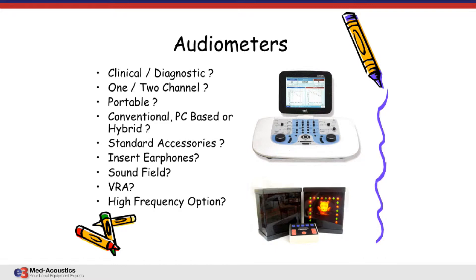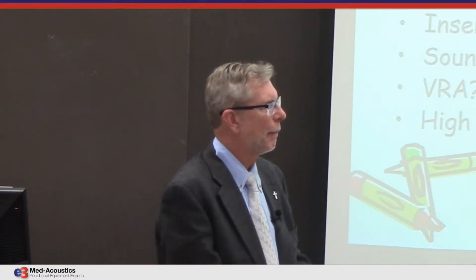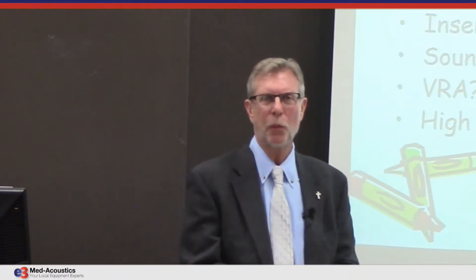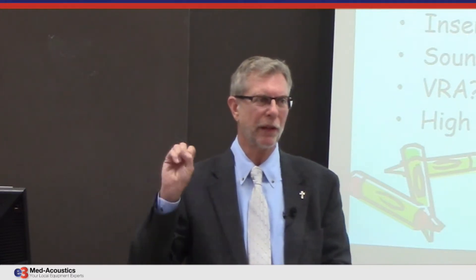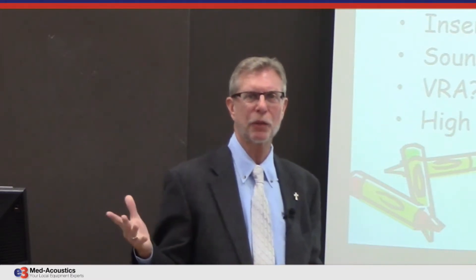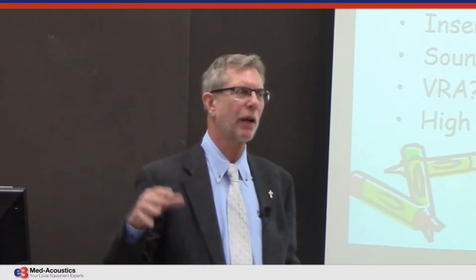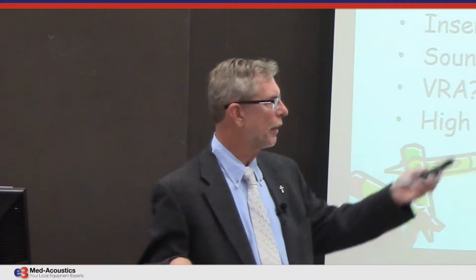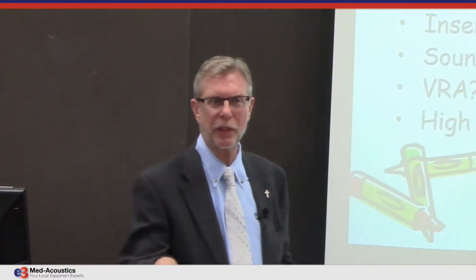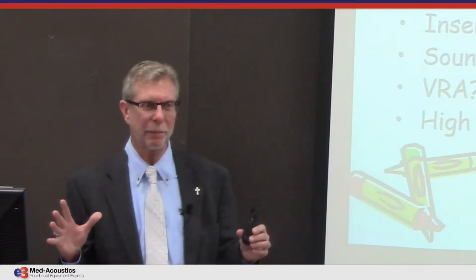The most popular type nowadays is a hybrid — it's both. It looks and operates like a conventional audiometer, and you can still draw audiograms on a test report form. But you can also hook it up to a computer. When you finish your audiogram, you can hit data transfer and it pops into software, which then creates a patient report that transfers into electronic medical records. If the computer goes down, it still operates — though nobody's going to like having to draw an audiogram.